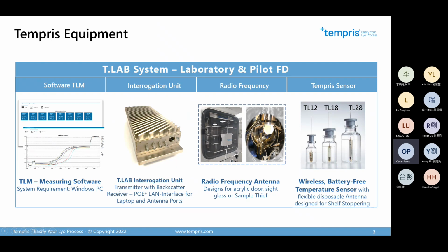The system will look quite similar to before. The software is the same, but with the basic functions. Normally, we also have pilots with the complete software requirements and IQ, OQ documentation and execution. And then the interrogation unit, the main system, does not need to be encapsulated because it's not installed on top of the freeze dryer chamber with the rest of the instrumentation, and it's a mechanical room, not a clean room, or let's say a desk area. So that's why we use this housing, which could also be fixed on the wall or put on top of the desk near the freeze dryer door.